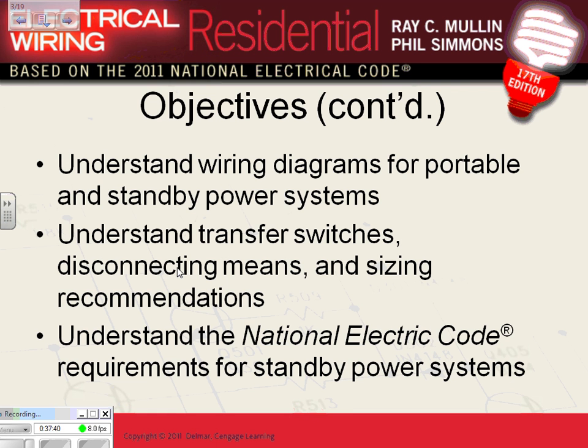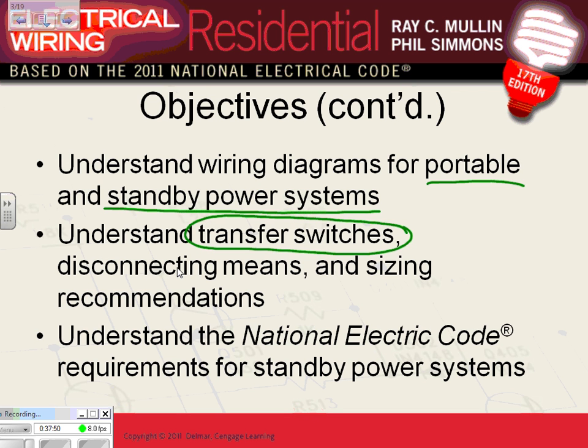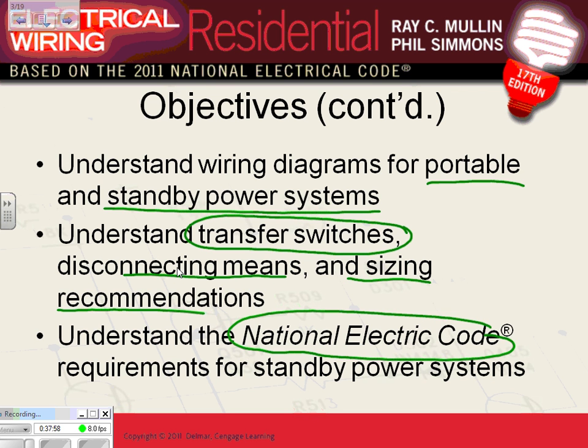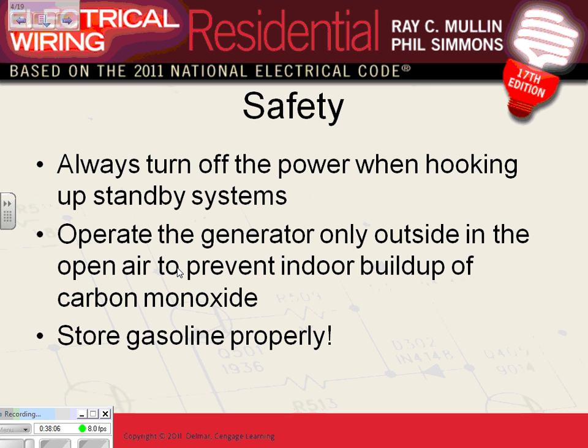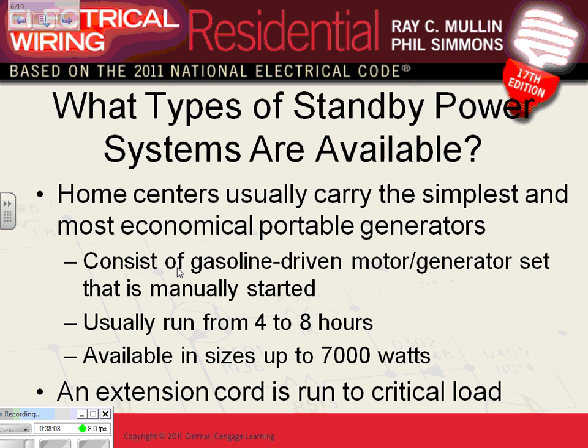Diagram for portable standby generators. So we're going to have a portable generator. You're going to see a nice picture of it. And a transfer switch, so you can transfer from one source to another, and a means to disconnect the power, as well as sizing the equipment, a big deal. And of course, the Bible always has to be consulted about everything that we do, right? The NEC code book has to be consulted about everything that you do. All right, the picture is really easier than said. I'm going to go all the way to my picture, guys.